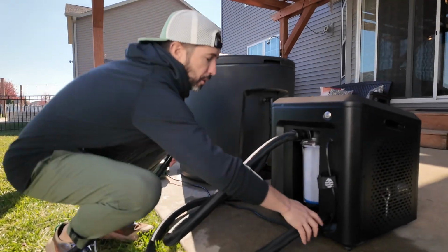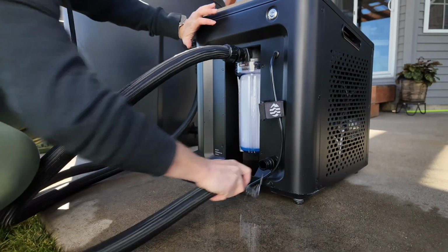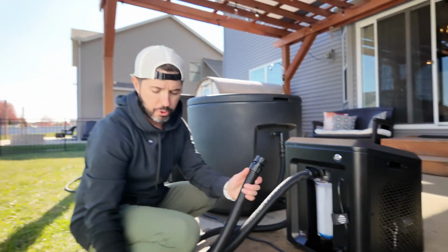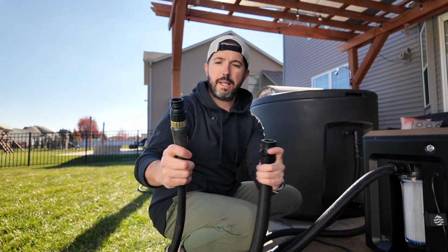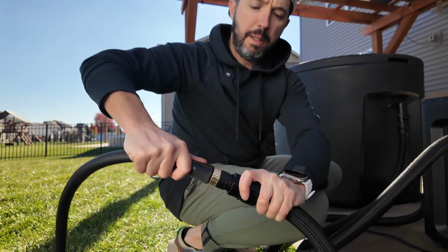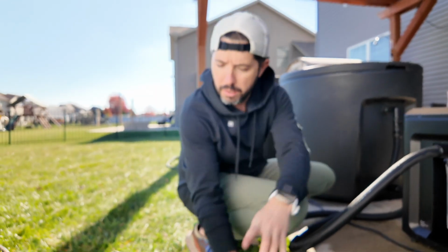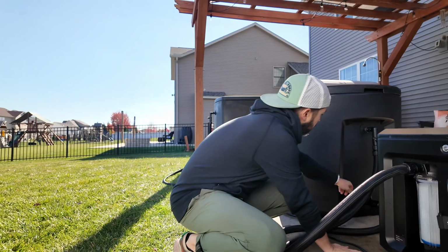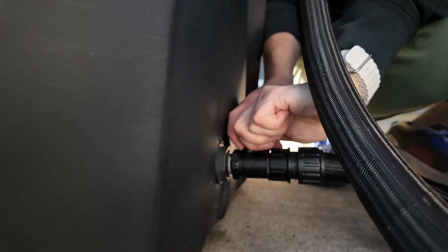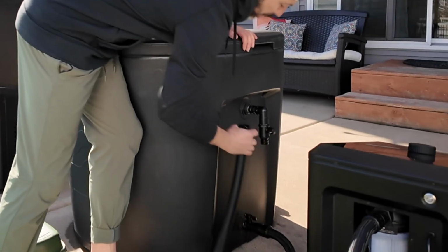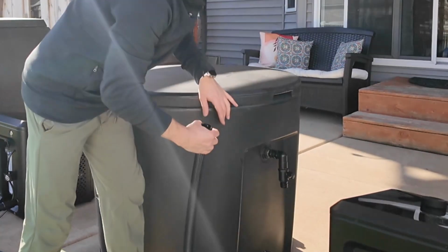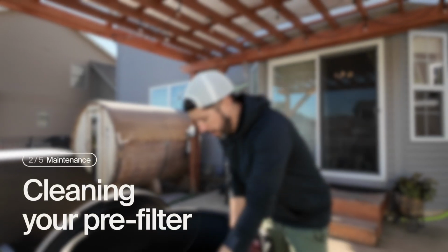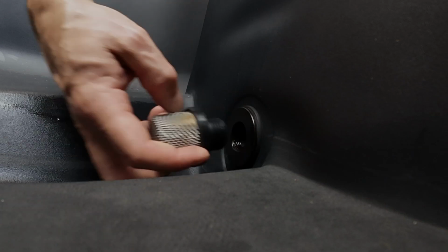With that valve closed, I can disconnect the bottom line from your chiller, connect it up to your garden hose, extending the quick connect hose to wherever you want, and then open up your valve. Once your barrel's fully drained out, you can disconnect the water lines. Now I'm going to clean the pre-filter, reaching down here to unscrew it.